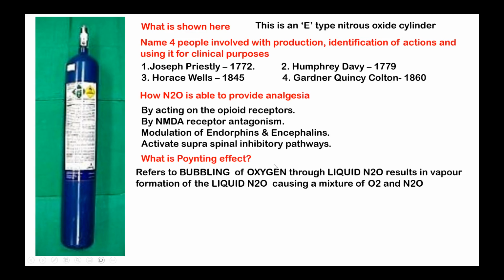What is the poynting effect? It is the bubbling of oxygen through nitrous oxide. Nitrous will show constant pressure until all the liquid is vaporized. Nitrous oxide is usually a liquid at room temperature. Okay. So in order to vaporize that, if you bubble oxygen, which is the gas, through this liquid, then nitrous oxide will also become a gas, and it will contain a mixture of both oxygen and nitrous oxide. So that is called the poynting effect. Compare the properties of oxygen, nitrous oxide, and air.